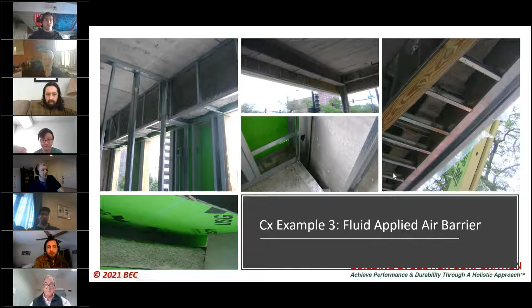Okay, retro commissioning. The difference between this and commissioning is that the building is existing, out of warranty, contractors demobilized for maybe a year, 2, 5, 10, or 50 years. You need to go in and commission it, test it to see if it actually meets the original design intent, or what it's being used for now. This can be more difficult, but also more fun.